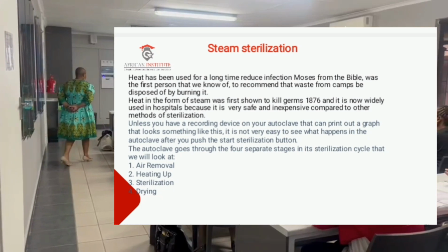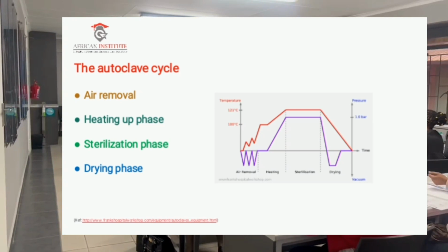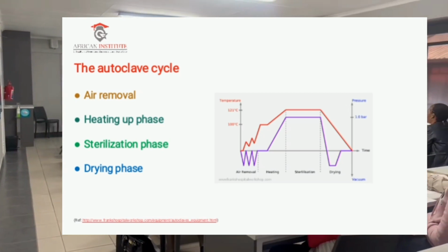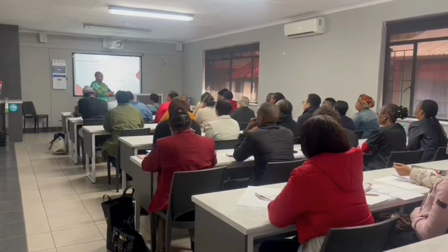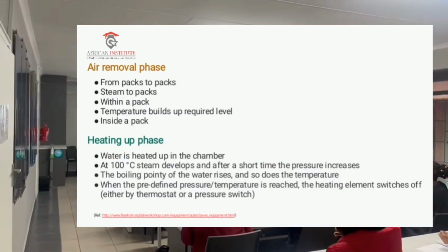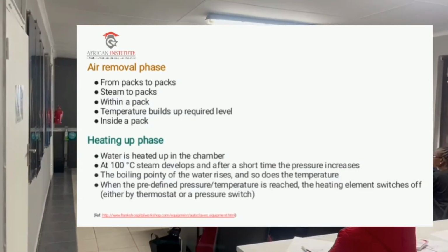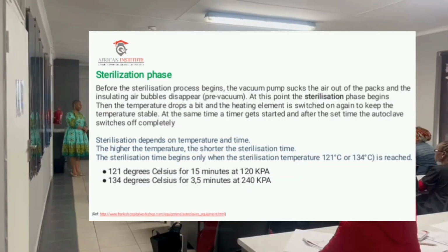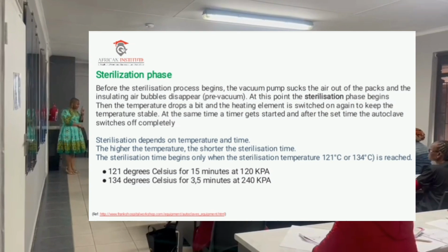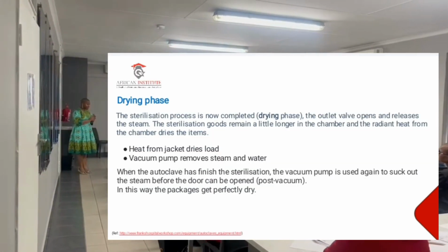Unless you have a recording device on your autoclave that can print out a graph that looks something like this, it is not very easy to see what happens inside the autoclave after pushing the start sterilization button. The autoclave goes through 4 separate stages in its sterilization cycle: air removal stage, heating up stage, sterilization stage, and drying stage.